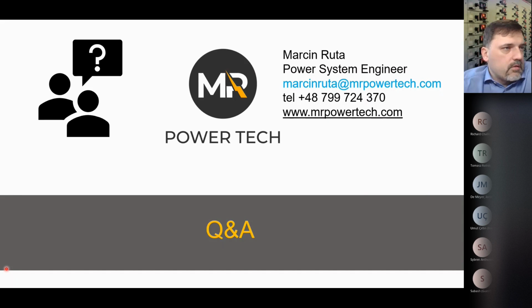Can we adjust these settings remotely, for example, before entering the electrical room? Yes, actually it makes sense. That's how it's sometimes done. There is a separate switch on-off, like 22mm switch on-off, maybe control panel, which you can, for example, when you enter substation or enter station, activate it, lock it, and when you are entering, you already know the energy is lower. So if you have a remote option, that's very nice. Sometimes it's just on the doors of the switchgear, but still you can do. It's not a big thing, but it's much better when you have it in some other place.